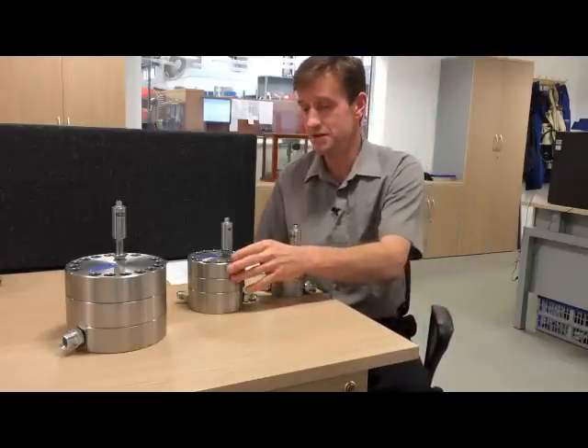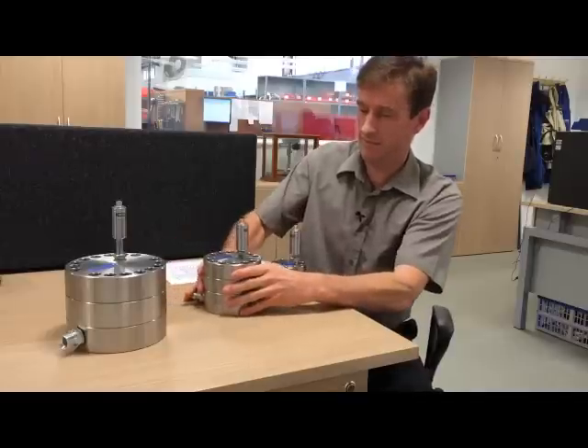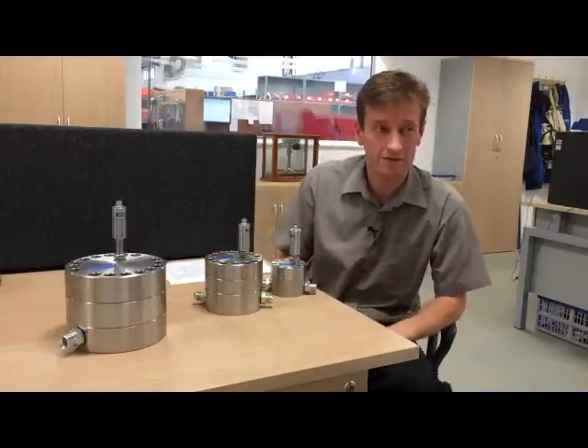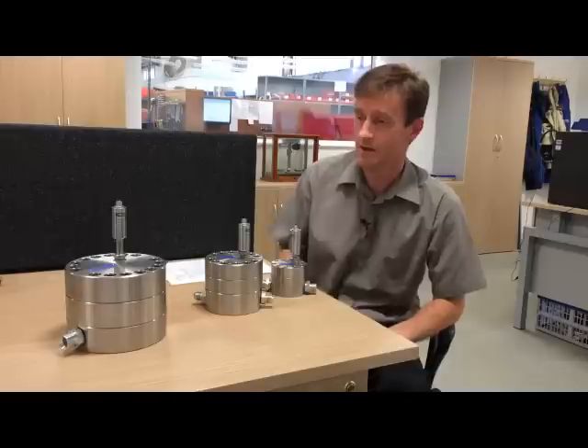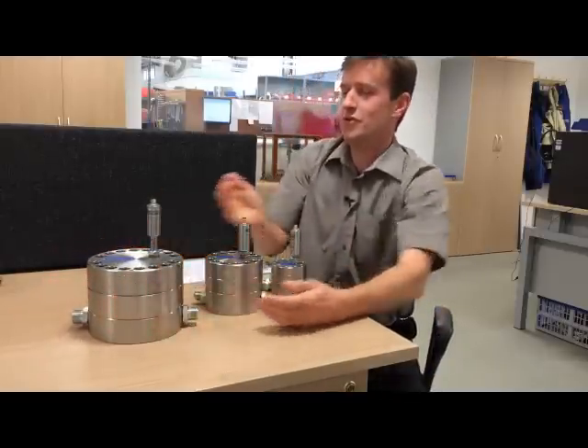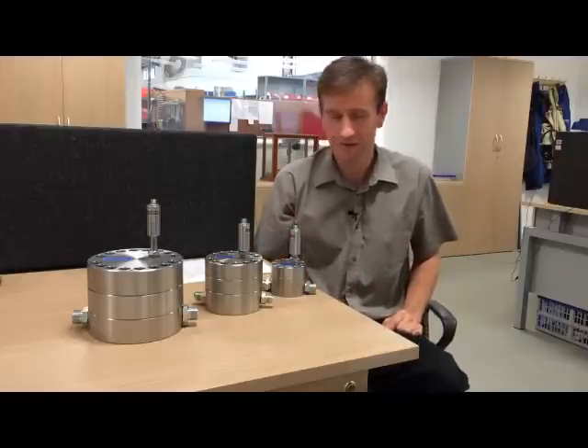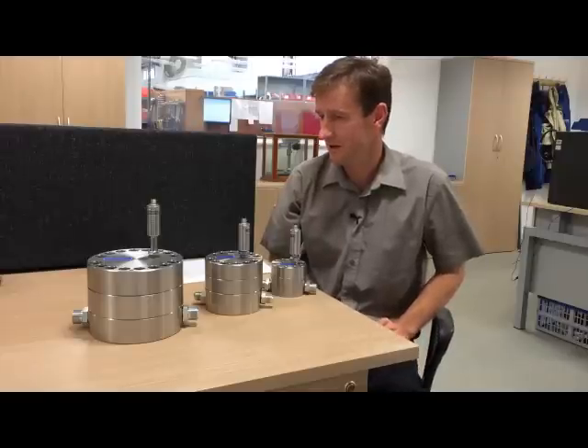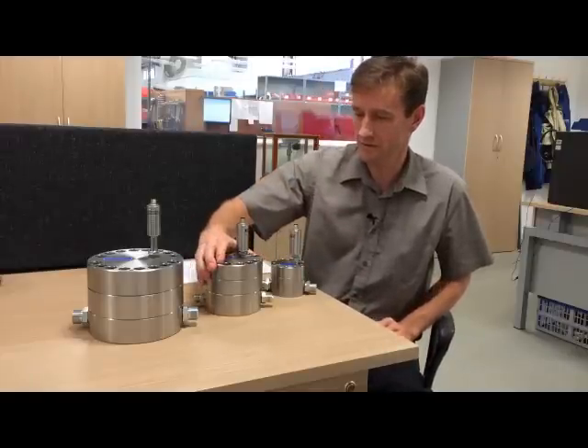The next one in the range is a medium-sized one here, and that is 0.5 liters to 70 liters a minute. And then the larger one, which we can move about, it's not too cumbersome, but that range is from 5 liters to 150 liters a minute. All the units are in 303 stainless steel.